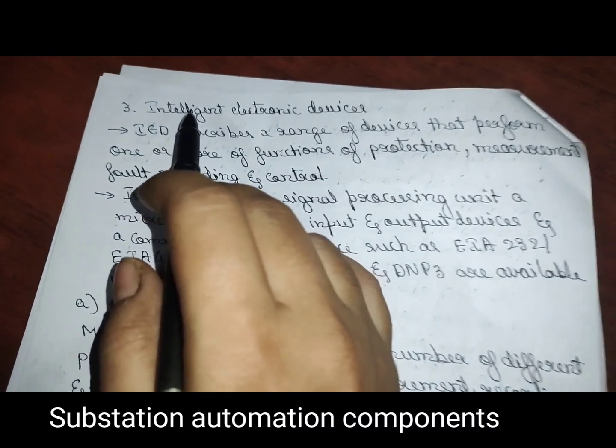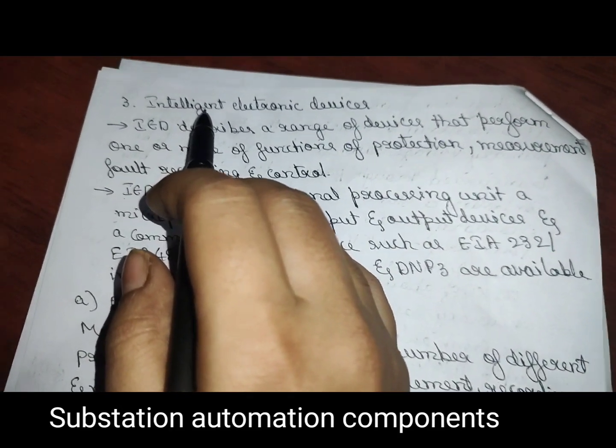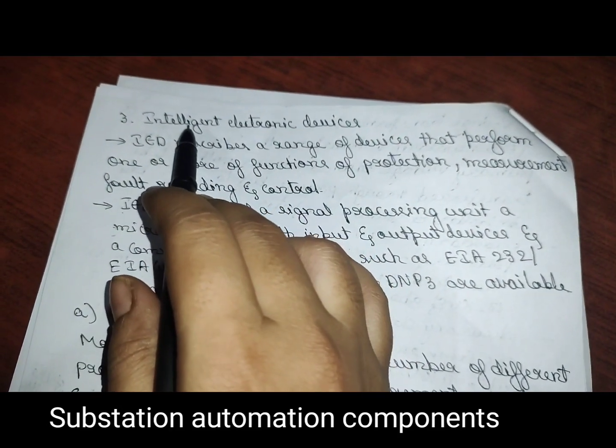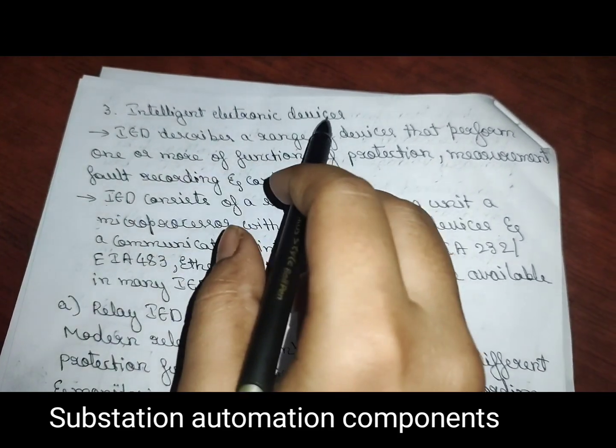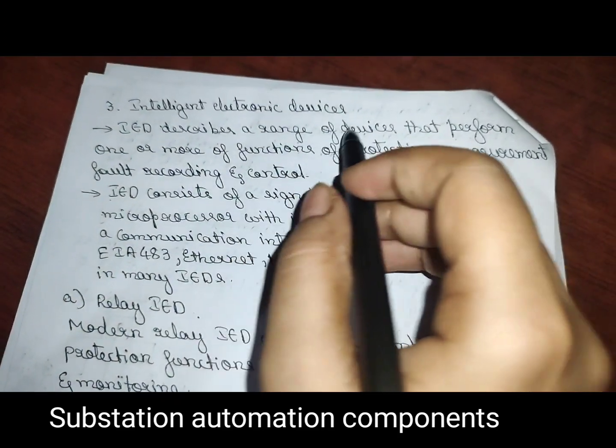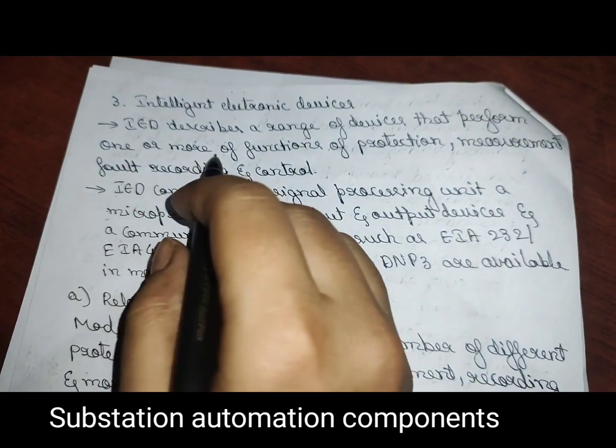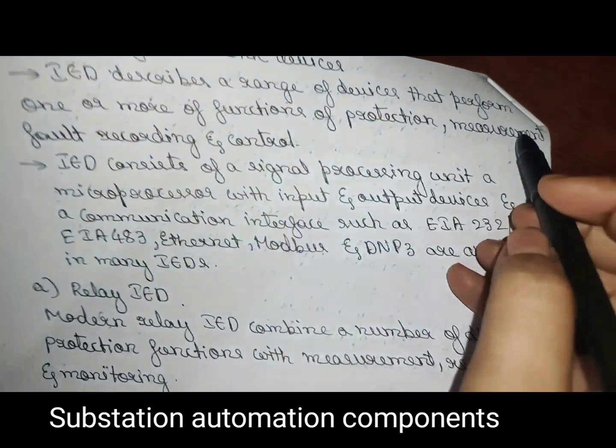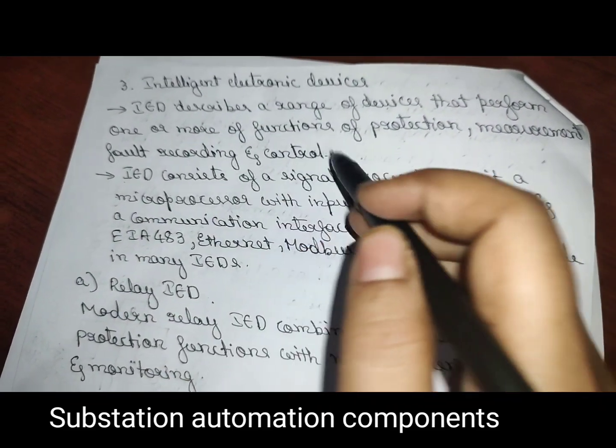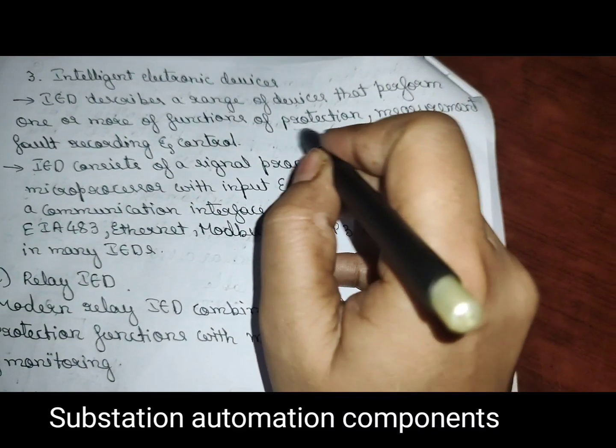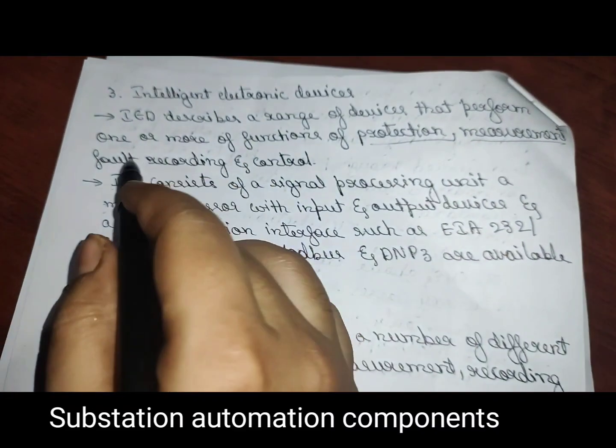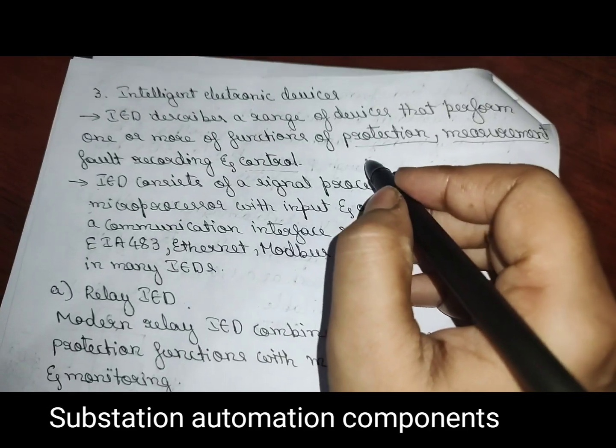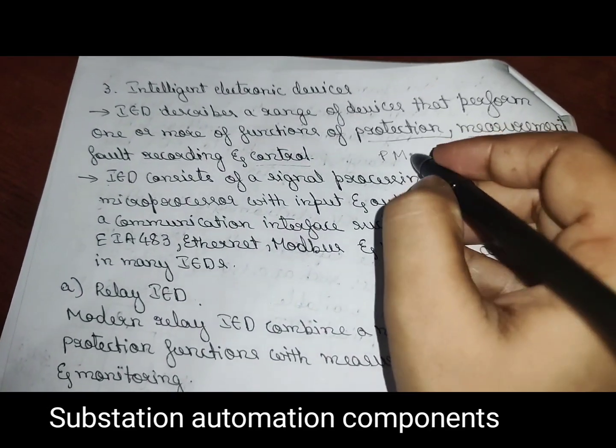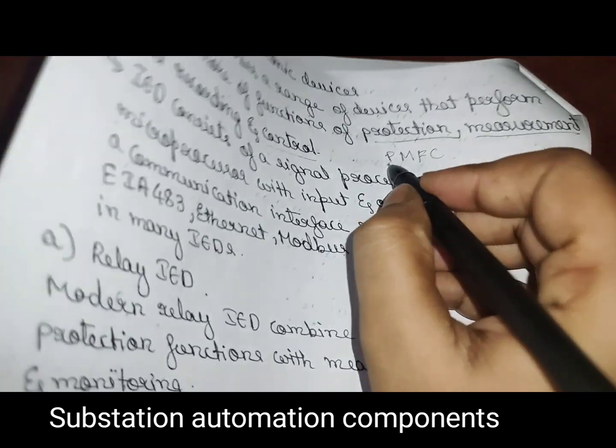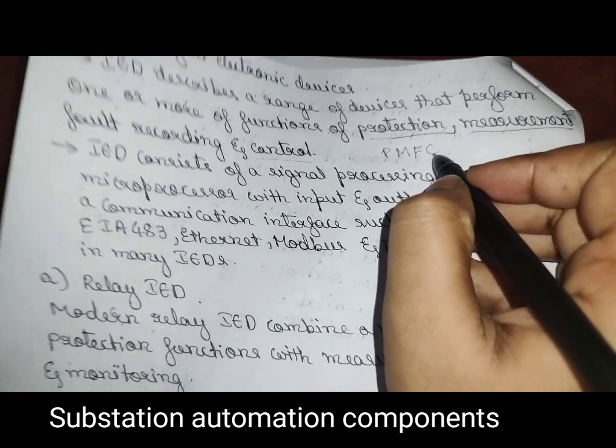Of substation automation, that is third one. First we have discussed CT and next we have discussed VT, that is CVT. So this is second and third is the intelligent electronic devices, that is IED. It describes a range of devices that perform one or more functions of protection, measurement, fault recording and control. So you can remember PMFC, that is protection, measurement, fault recording, control.